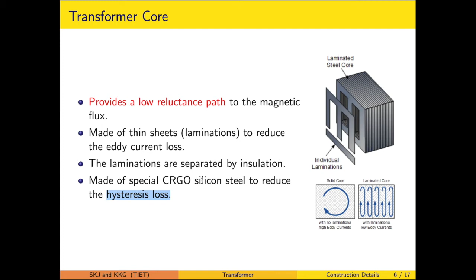Another aspect is that this magnetic core also provides mechanical support to the transformer. Beyond this mechanical support, the objective is to provide a low reluctance path to the flux. Reluctance is analogous to resistance in electrical circuits. When the reluctance is low, it is a convenient path or medium for the magnetic flux. The core is also made of high grade CRGO silicon steel. The silicon is added to reduce the hysteresis loss, where CRGO stands for cold rolled grain oriented. In this, the laminations are cut along the rolling direction.